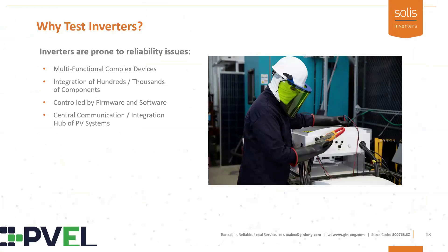So continuing this concept of why testing inverters, I really like to make the comparison back to certification testing. Certification testing is typically performed on a single sample. So you have a single product provided by a manufacturer to a test body, UL, CSA, TUV, one of these test bodies, and it's primarily focused on safety and integration integrity testing. We're not looking at long-term wear out, we're not looking at midlife wear out, we're really trying to understand if this product is safe to be installed in a residence or a commercial operating facility.